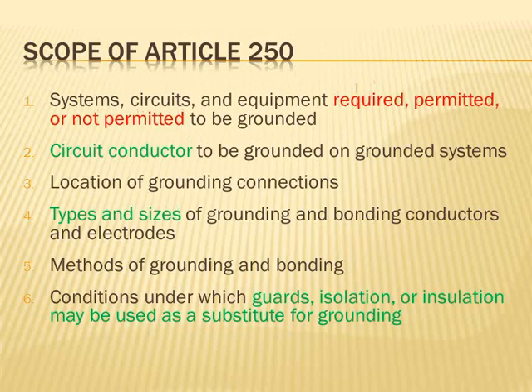Okay, scope of the article. This talks about, very interesting, when you go there, required, permitted, and not permitted. The NEC requires you to ground the system if you bring it to a building. If you don't bring it to a building, we don't care. Permitted is up to you, or not permitted, you cannot bond it. Circuit conductor to be grounded on grounded. If you have a delta, which conductor can you ground in a delta?